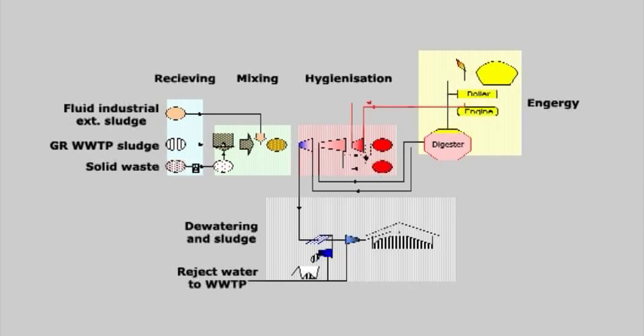Before and during mixing, solids are broken down, mixed with slurry, and then mixed with the industrial waste before being sanitized at 70 degrees C, cooled to 40 degrees, biogasified and dehydrated before the residues are stored in a tank which can take a full year's production.